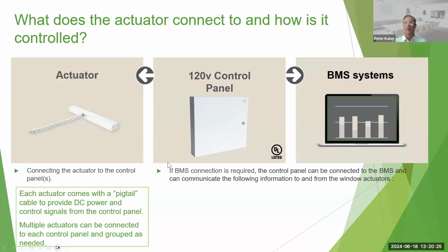Typically, if you've got a typical 1 amp actuator and say a 20 amp control panel, you can have up to 20 windows, single actuator windows, operated by a single controller.